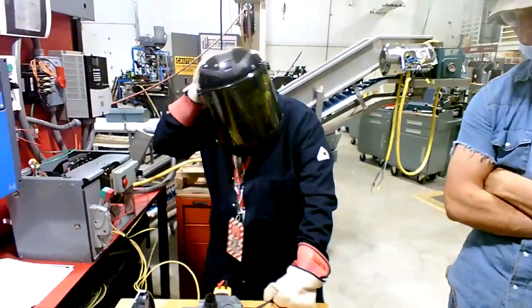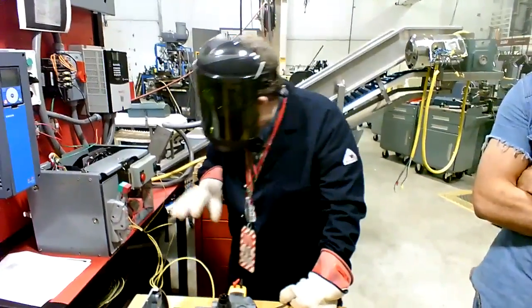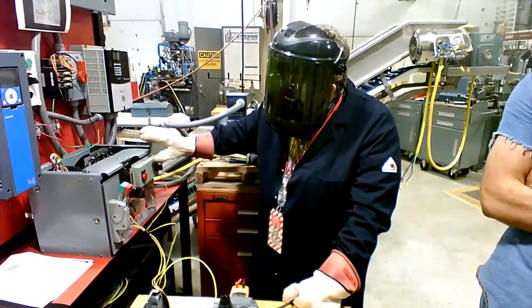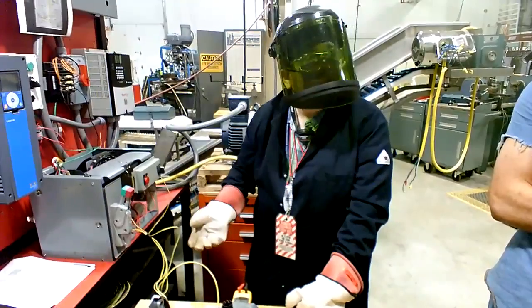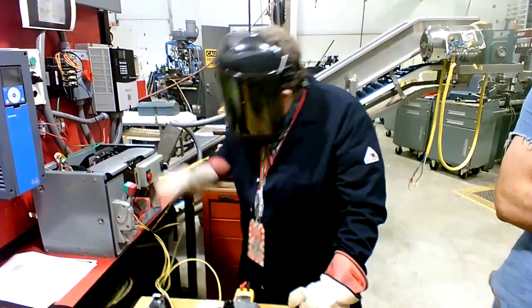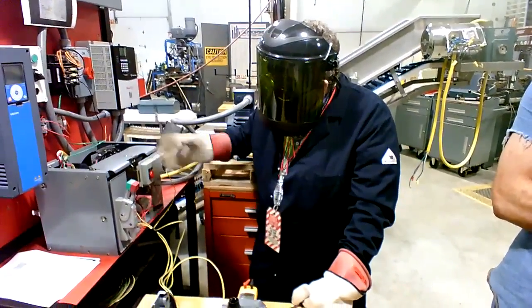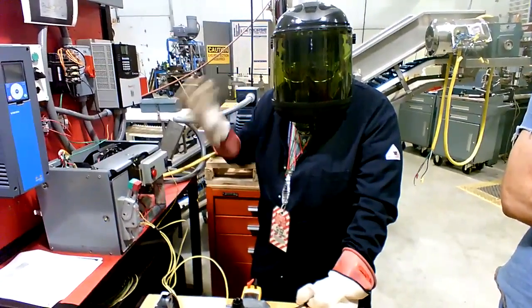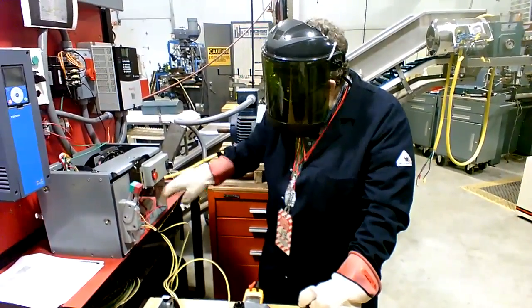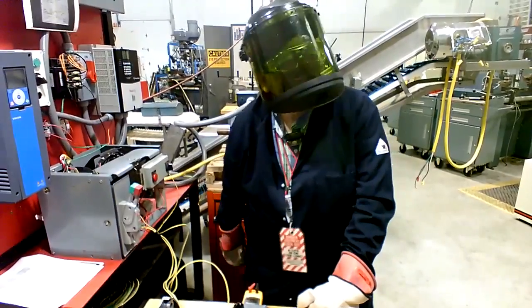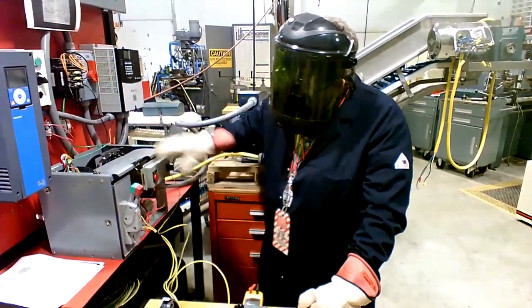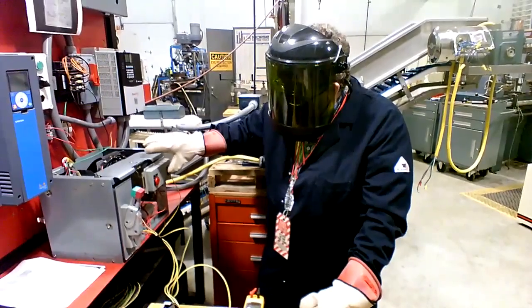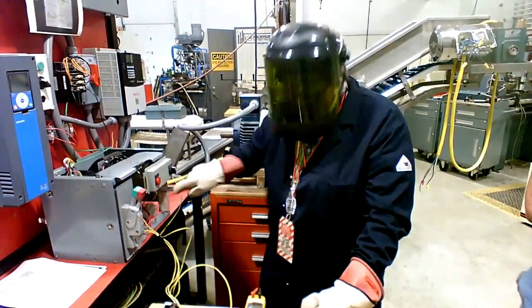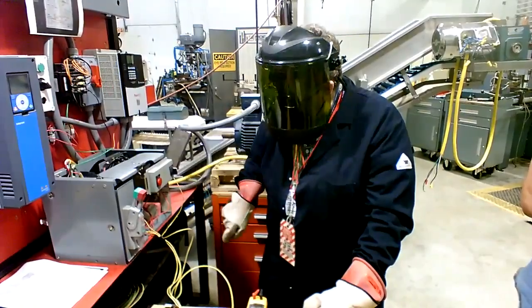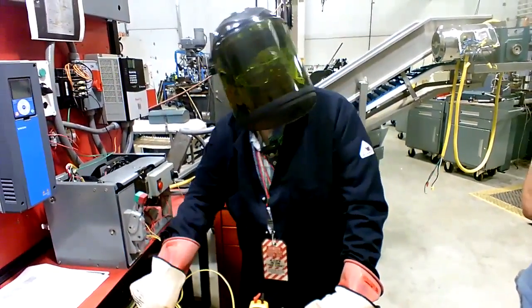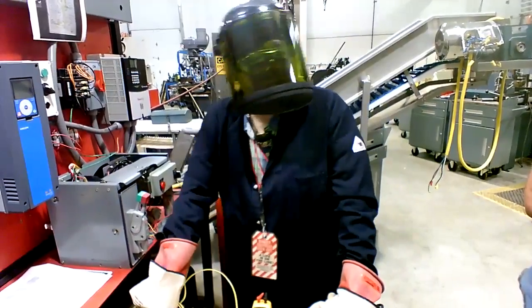Okay. Now, when you get in the plant, some departments run all their motors on 480 volt, and some departments run them on 240. So it depends on where you are. Here, you saw what the riggers are. If they say it's a 480 volt motor, it's going to be 480 volt leg to leg. We said leg to ground. If this was a 240 volt power source, it would be 240 volt leg to leg, but leg to ground, it would actually be 120. You kind of keep that in mind.